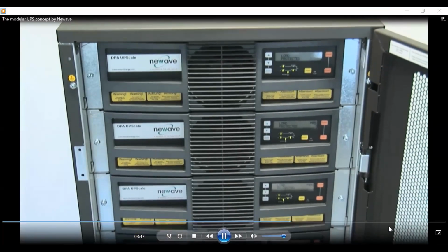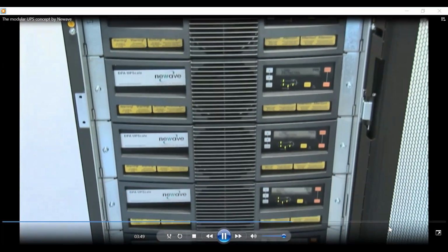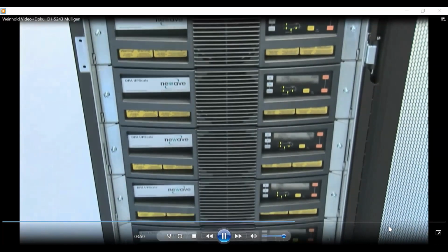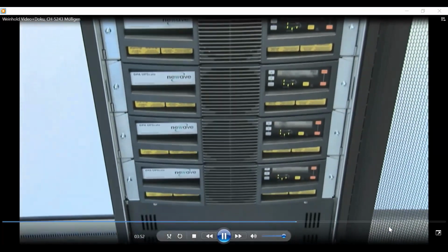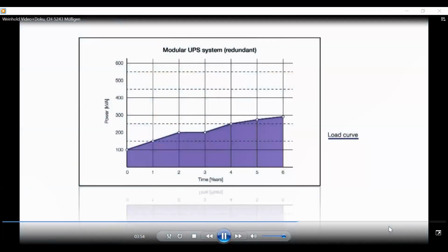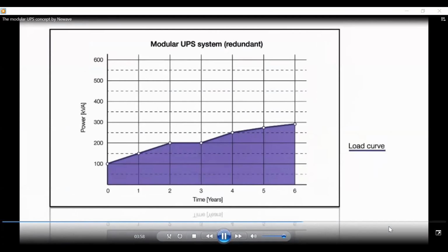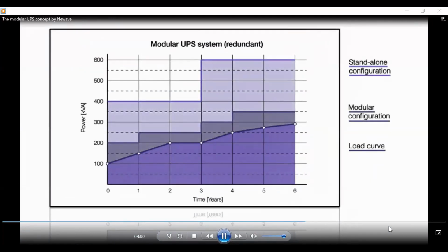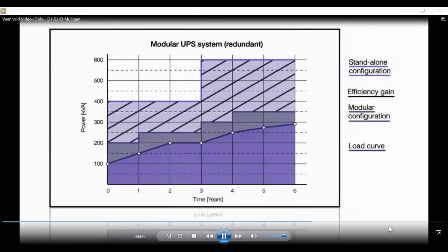Modern modular rack-mountable UPS systems eliminate the disadvantages of the large system approach, since the UPS system can be scaled in one of two ways, either vertically or horizontally. This right sizing reduces initial cost, optimizes operating efficiency, reduces floor space requirements, and helps decrease total cost of ownership.